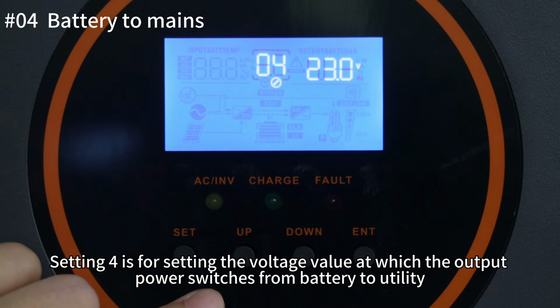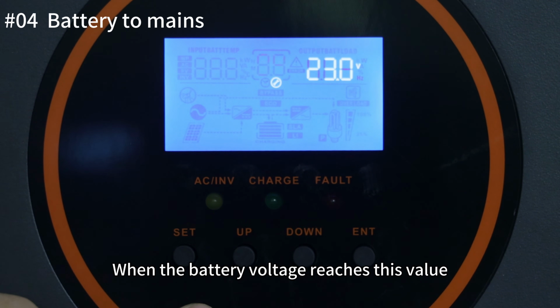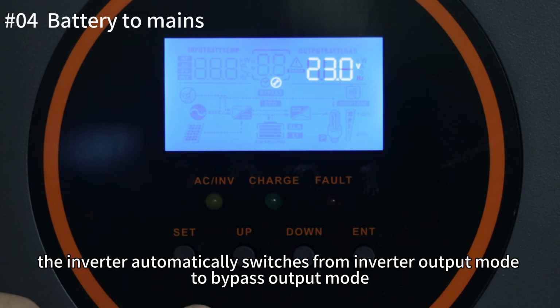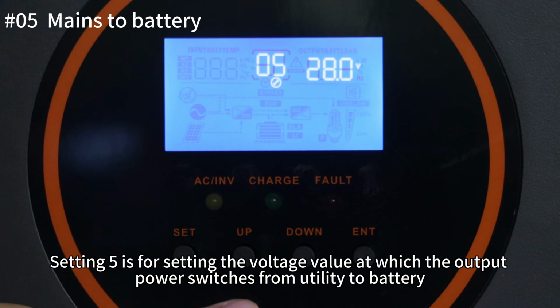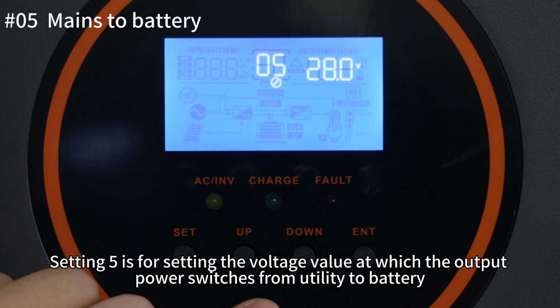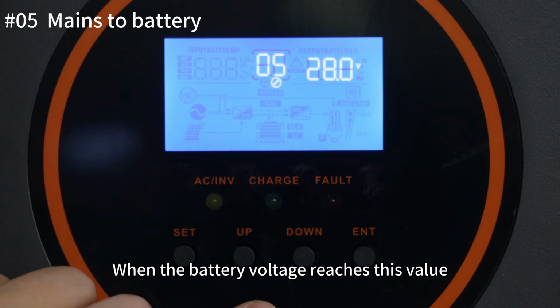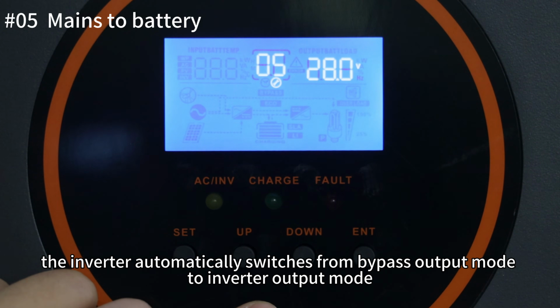Setting 4 is for setting the voltage value at which the output power switches from the battery to utility. When the battery voltage reaches this value, the inverter automatically switches from the inverter output mode to bypass output mode. Setting 5 is for setting the voltage value at which the output power switches from utility to battery. When the battery voltage reaches this value, the inverter automatically switches from the bypass output mode to inverter output mode.